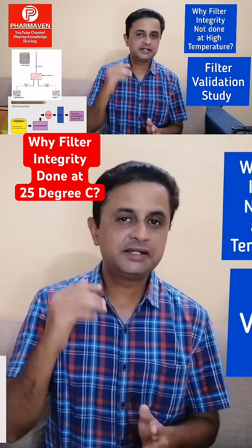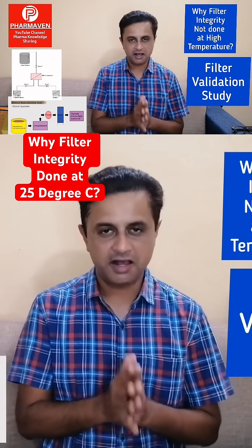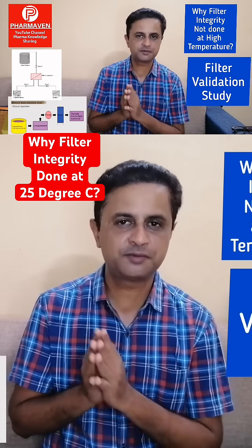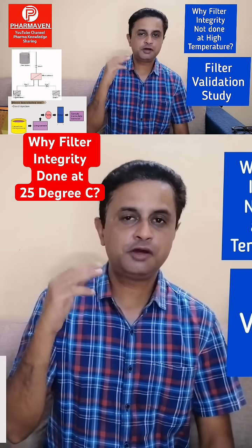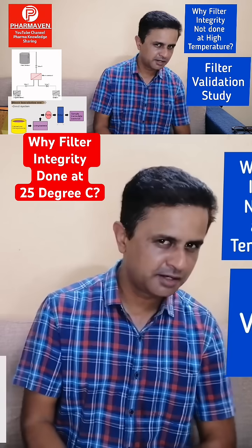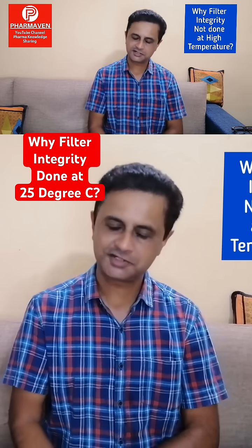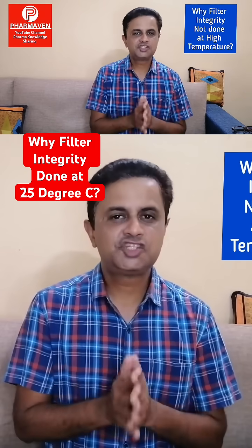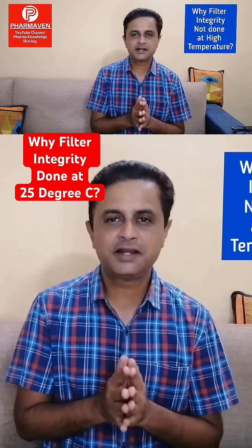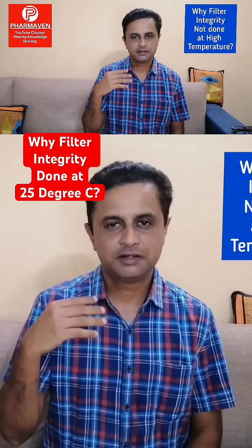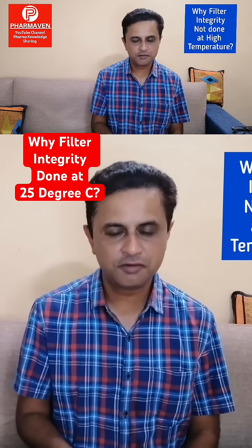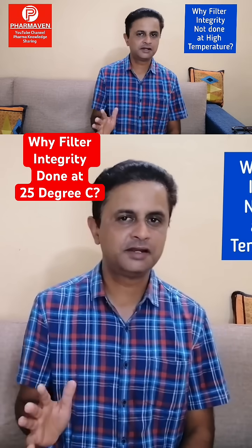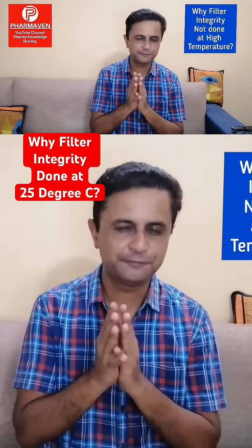So each of the integrity values which are derived are for each specific product. So if you are working closely, if you know the filter integrity values well, you will understand that each product has a different filter integrity value. Let it be bubble point or forward flow, it has a different filter integrity value. From product to product, it varies.